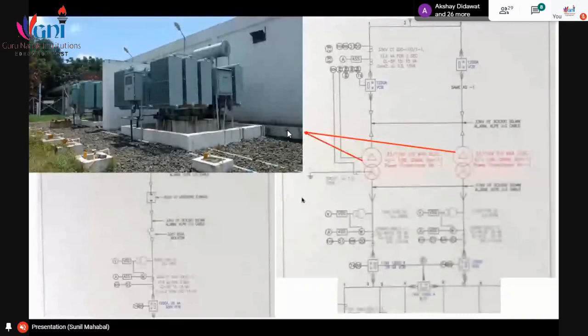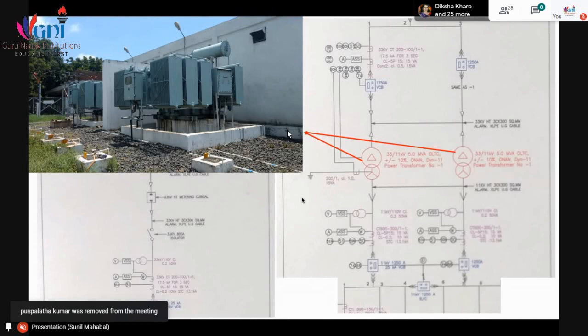The reason is that earlier our factory was fed with 11 kV supply from MSCB. So therefore, the entire circuit was of 11 kV. The distribution was of 11 kV. But our contract demand increased because of the increase in the connected load. Then MSCB told us that now you have to upgrade your incoming voltage and go to 33 kV. So we had to install these two transformers and we kept the distribution as it is at 11 kV.